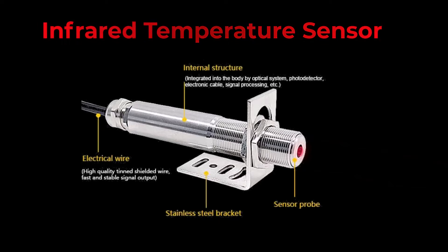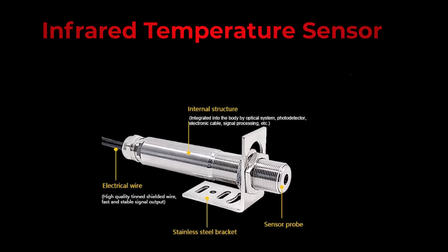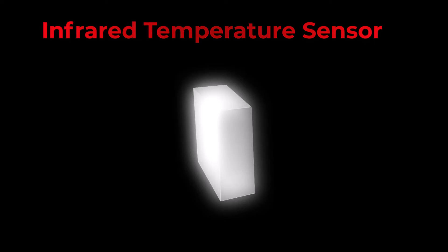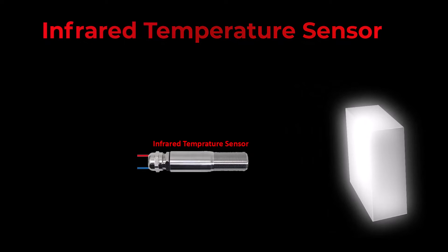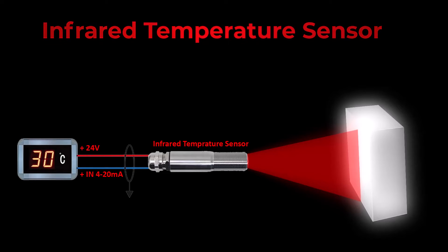Industrial IR thermometers have an extensive temperature range, usually between minus 50 degrees Celsius and 1000 degrees Celsius. All objects with a temperature above absolute zero emit infrared radiation, and the intensity of this radiation is directly related to the object's temperature. The infrared sensor consists of a lens that focuses the infrared radiation onto a detector, which converts it into an electrical signal. The electronics then process this signal to calculate the object's temperature based on the intensity of the detected radiation.